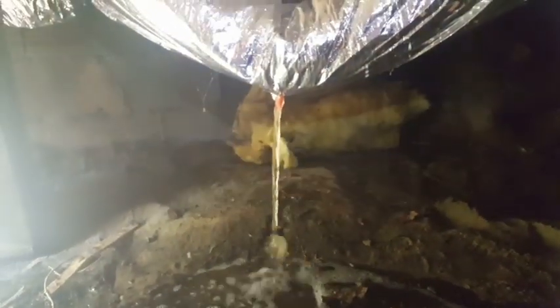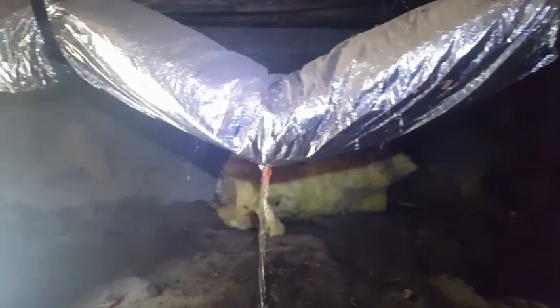You guys can see this one I actually had fallen down because of the weight of the water on the insulation. So we'll see. We're going to have to drain some of this stuff out, but not looking too good for these ducts. Probably ought to be changed, but at least we'll drain them out while we're here and test out the system here. Oh look, whee! Build a dam down here. Not good. All the insulation's falling down, taking down some of the ductwork. One of the boots is falling down. Not good. I accidentally let it go in the hole. That wasn't too swift.